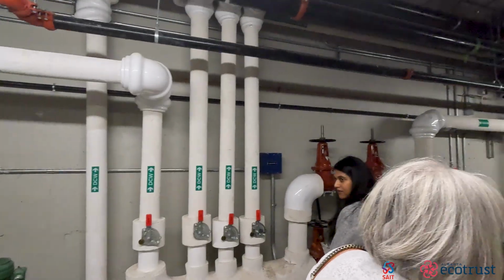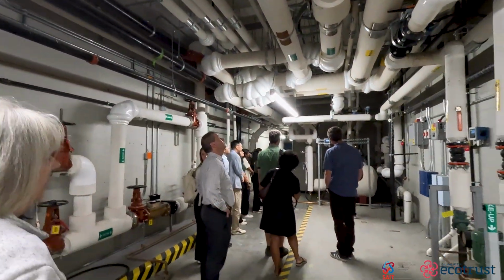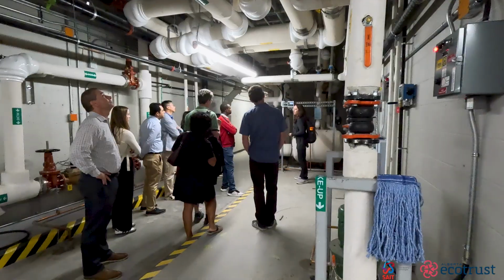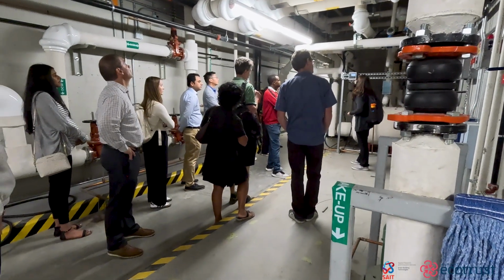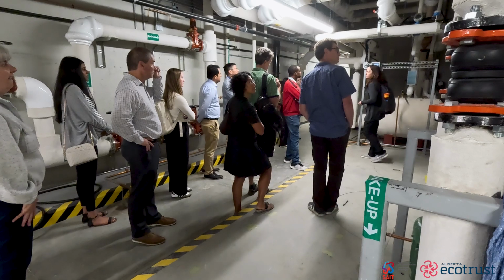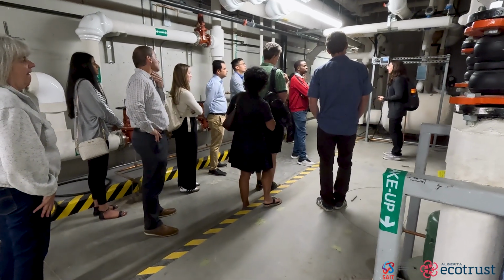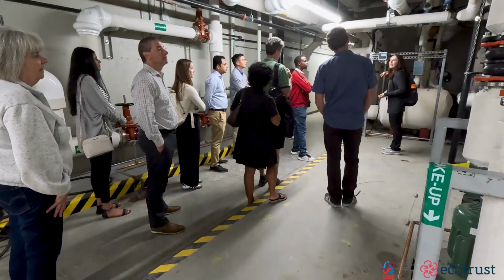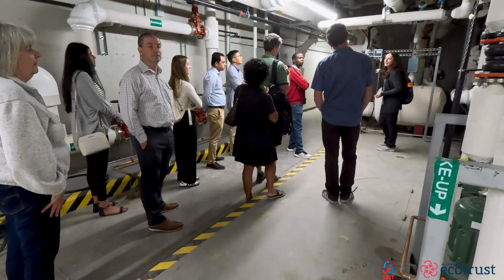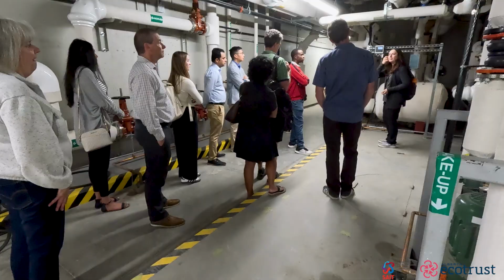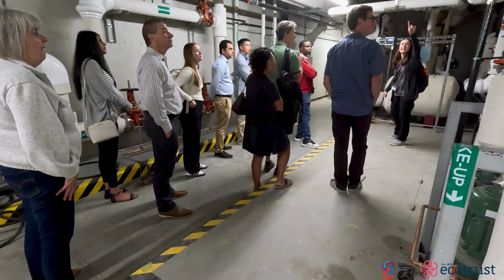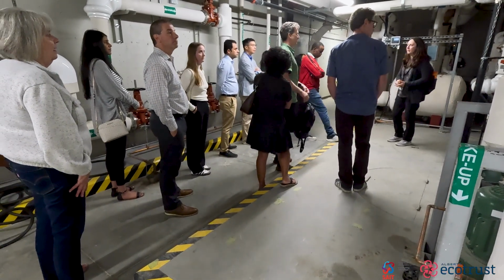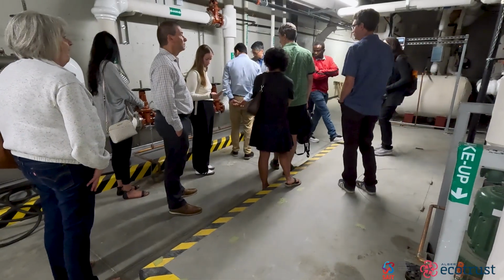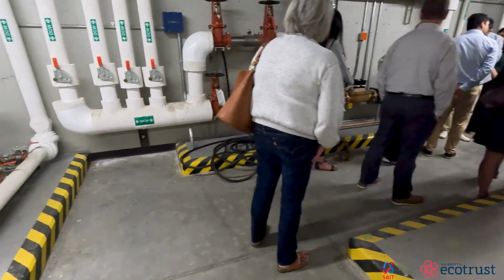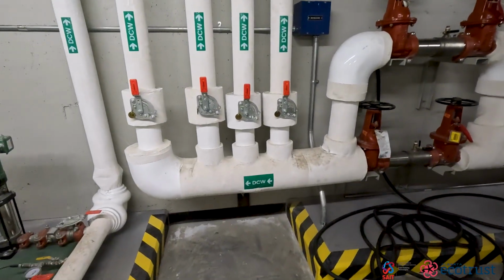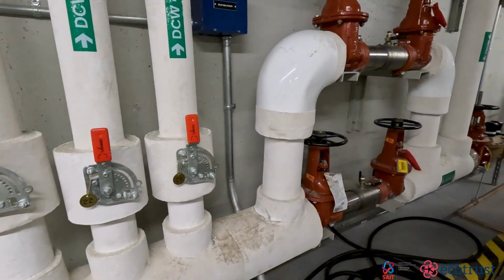So it's not very big. These are thermal meters—they have two temperature sensors and a flow sensor, and it's just pure thermodynamics where you calculate the amount of energy sent to a certain system. All this is connected to our BMS system. We have one for the main heating, one for domestic hot water heating, and then the more traditional one behind you—that's our main water meter, a dual head Neptune turbine meter, also connected to our BMS system, which we use to monitor total water usage in the building.